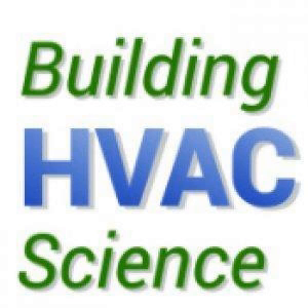So you would take a large fan, the blower door, and a cloth canvas that seals off the doorway, the front door, and you install the fan into the canvas. That creates an air barrier between the indoor and outdoor with the fan in between. Then you use a digital manometer to take a reference between outside and indoor pressure. You're also taking a pressure difference between the nacelle of the fan and the outdoors, so that you can convert the pressure in pascals across that fan into a flow, like CFM or cubic meters per hour. That gives you a sense of how much air is leaking out of the building, what the hole looks like in the envelope, the aggregate hole from the whole envelope leakage.